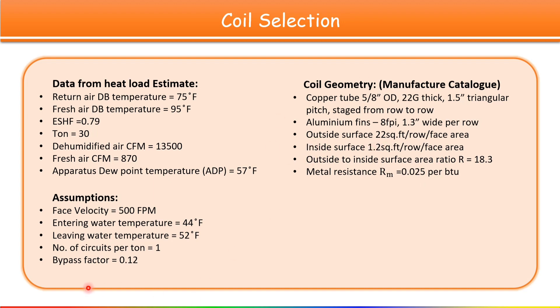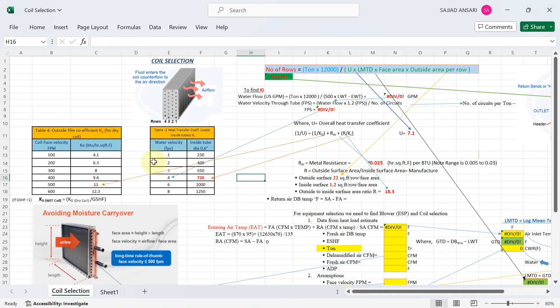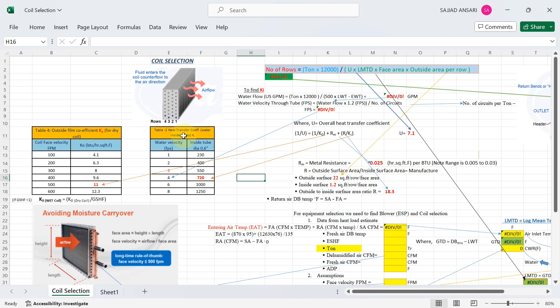Now let's start the calculation in the Excel sheet. As a designer, our main target is to submit certain details to the manufacturer for coil selection. Those details are: first, the number of rows of coil; second, the face area of the coil; and third, the dehumidify CFM value.